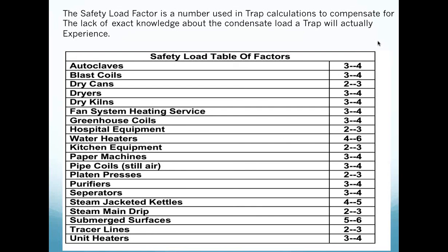And I do want you to know that I have seen a rash of problems when contractors come in and do any kind of work, and then they leave because everyone is in such a hurry to get the system back up and running that they don't give the contractor time to put all of the insulation back on the system. And I need you to know that if that insulation doesn't get put back on that steam piping, it will drastically enhance the condensation generation ability of that system, and you may or may not be able to handle it with the traps that were selected with the insulation on.